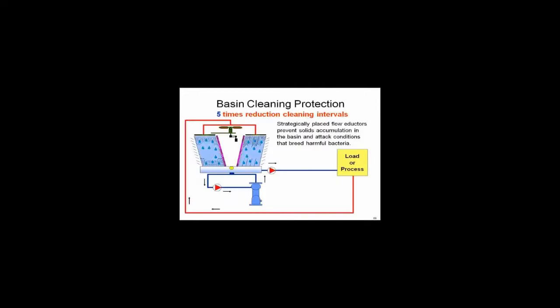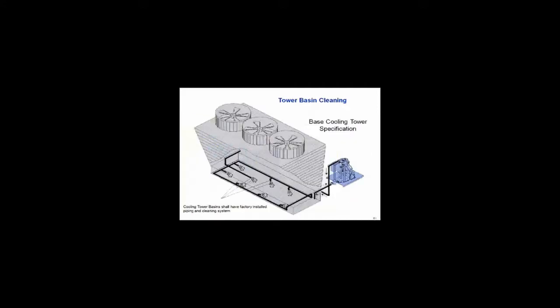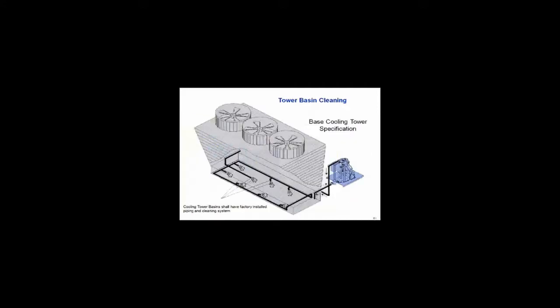Please consider putting separators, sand, centrifugal, whatever you want, to clean those systems up so we don't get problems. Here's a typical example of a little water-side cleanup where we're using the basin of the tower, a little sweeper type system to keep it clean. No big deal. Here's what it looks like. We even recommend that you, in your guide specifications on all cooling towers, that you get the factories to install these little piping systems for cleaning in the basins. You don't have to buy the sand filter now. You don't have to buy the centrifugal separator now. But get the sweeper systems in the basins of those towers so when the time comes somebody has a maintenance issue or somebody has the money, don't have the money up front, then go ahead and get this done because this is critical to making these things work. Why would we spend the money if we're not going to make them work? That's kind of the question.